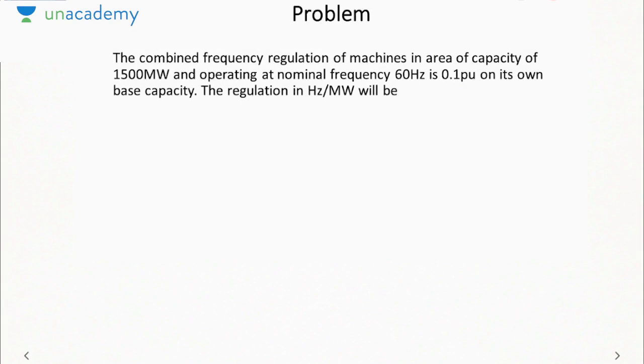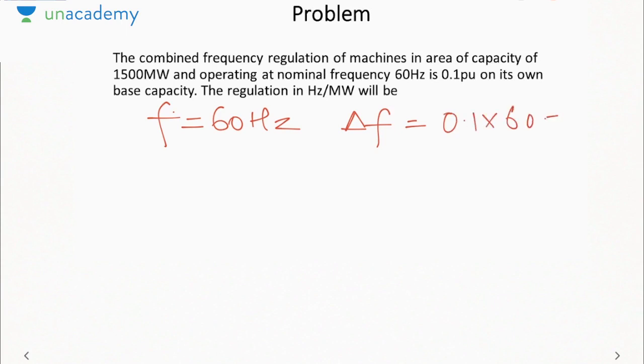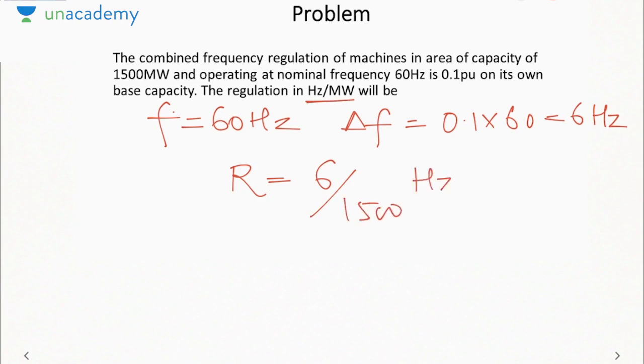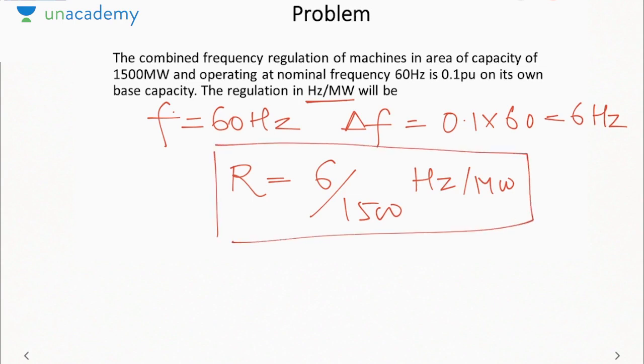In our next problem, it is saying the combined frequency regulation of machines in an area of capacity is 1500 megawatt. Frequency is given 60 hertz and frequency regulation is 0.1 pu. So what will be the delta F? That is 0.1 into 60, that is 6 hertz. Now we need to find regulation in hertz per megawatt. 6 by 1500 hertz per megawatt, because real power generation is 1500 megawatt and change in frequency is 6 hertz.